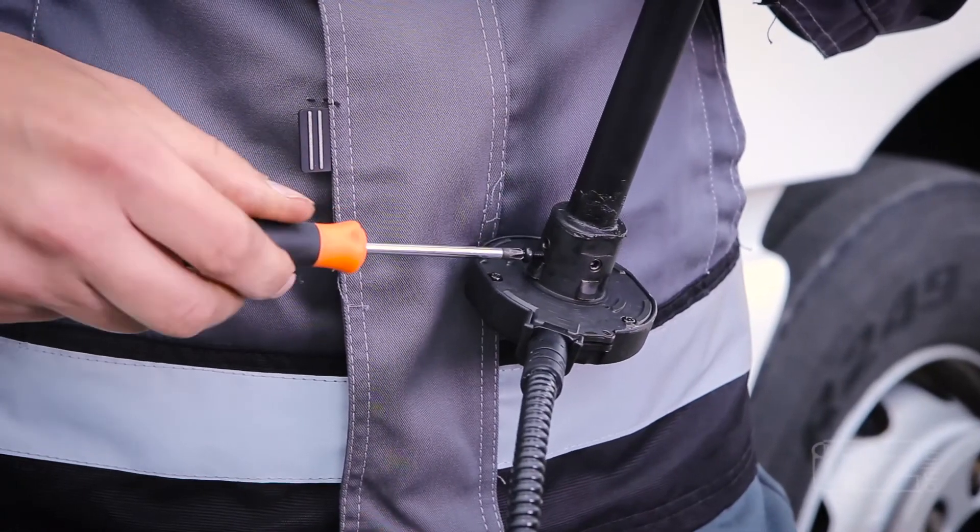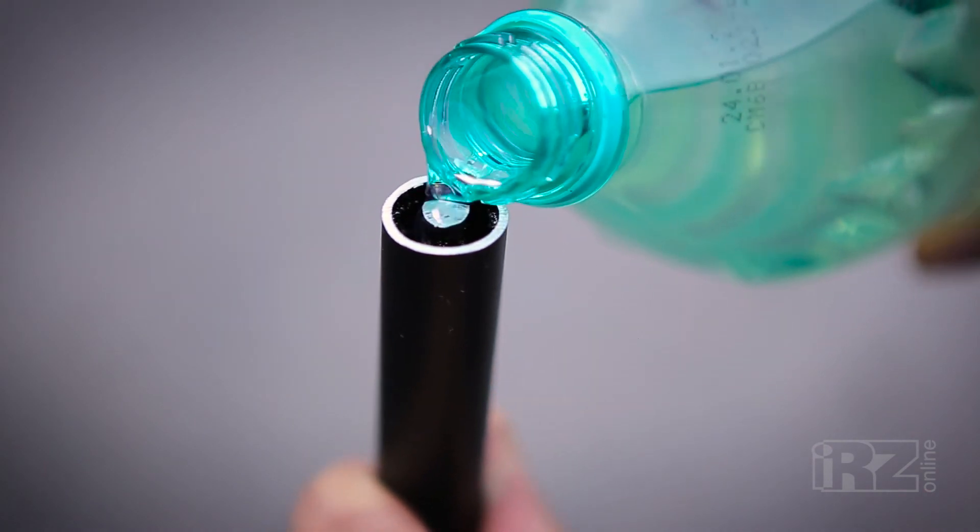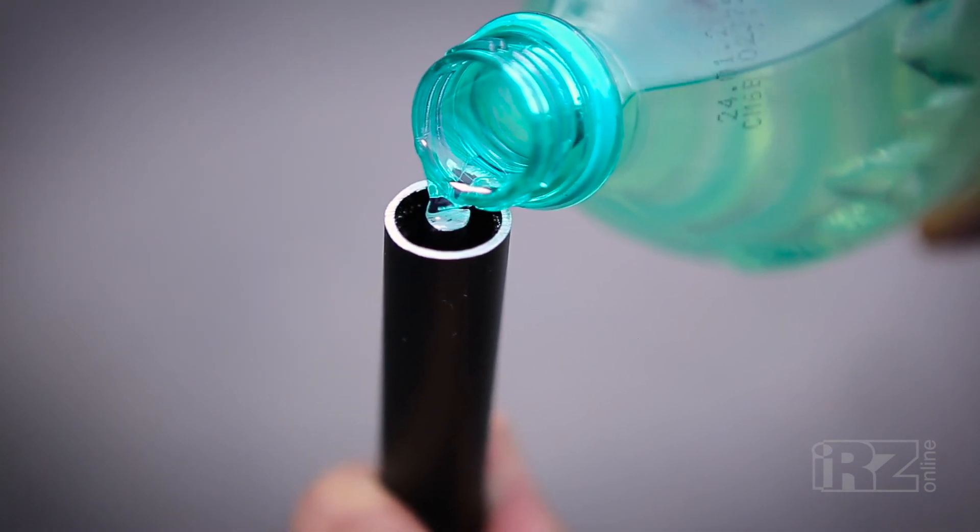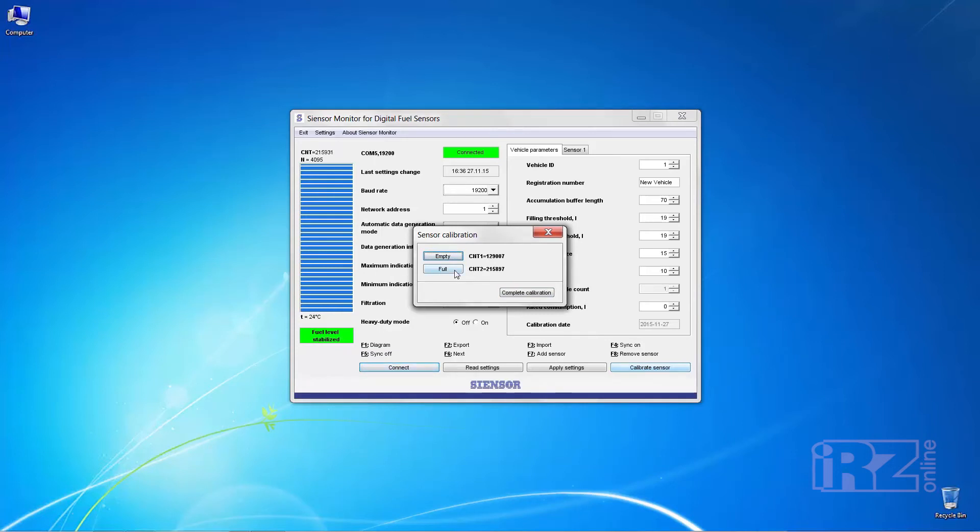Preliminarily, you should screw the supplied bolt in the drain port. Then fuel is poured into the probe. When the inscription stable level appears at the main window, you have to press sensor calibration. In the window sensor calibration you should press full. The value is fixed. Then fuel is completely drained from the probe. Drain port is open. When the inscription stable level appears at the main window, you should press empty in the window sensor calibration. Calibration completed.